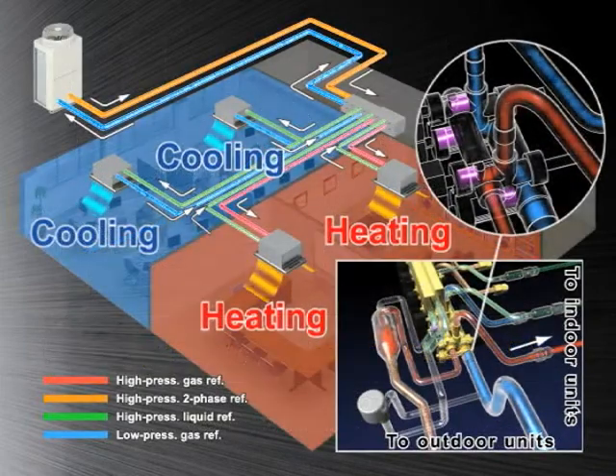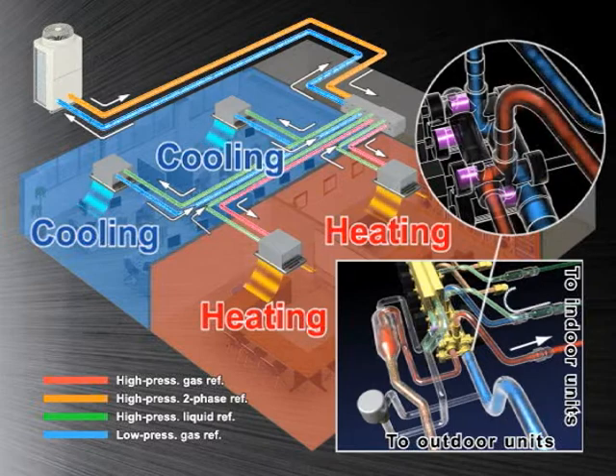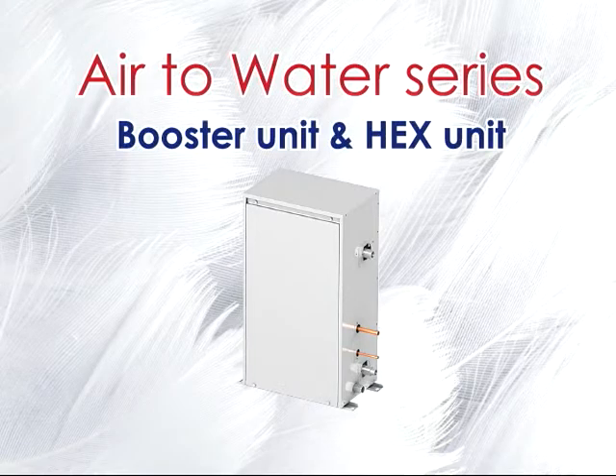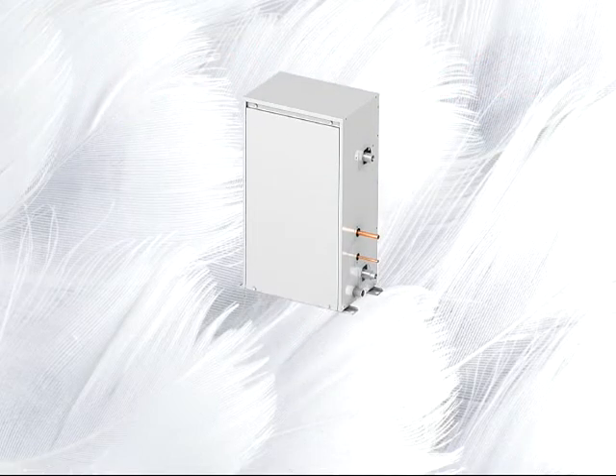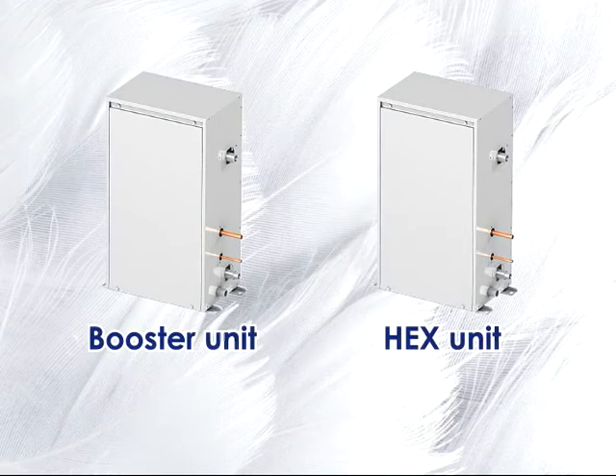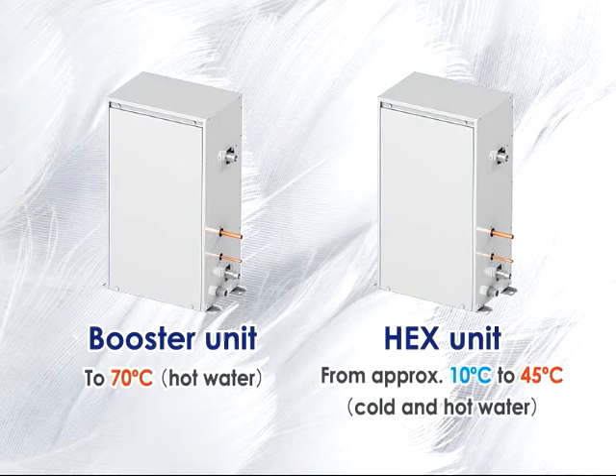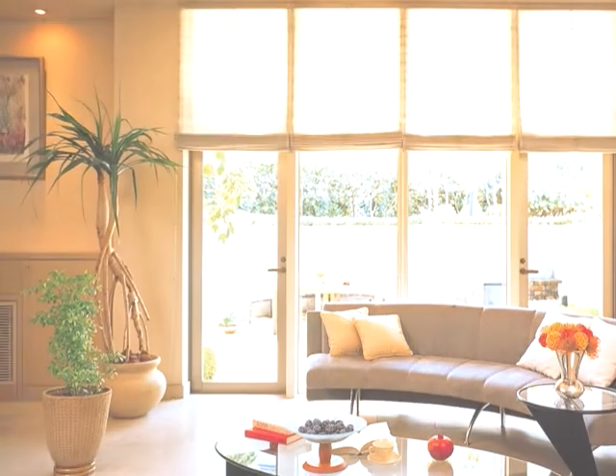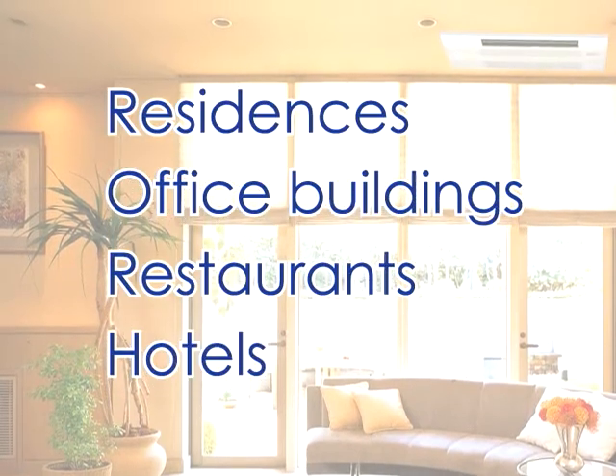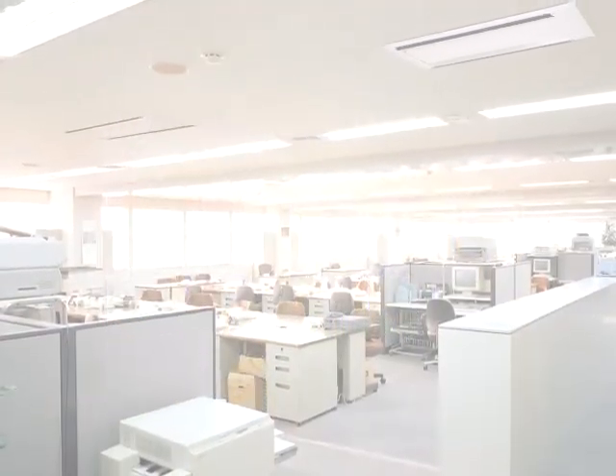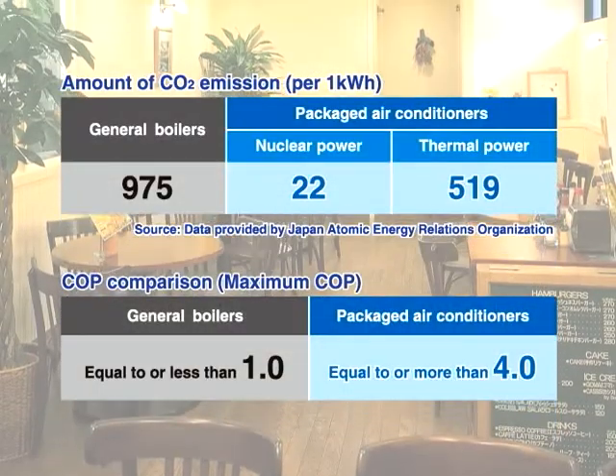This reuse of waste heat also applies to the air-to-water system, which supplies hot water with its heating cycle and utilizes the waste energy for cooling. The air-to-water series consists of 2 types: a booster unit and a heat exchanger unit. The booster unit offers hot water to a maximum of 70 degrees Celsius. The heat exchanger unit offers up to 45 degrees Celsius in heating mode and down to 10 degrees Celsius in cooling mode. Both units are suitable for residences, office buildings, restaurants, or hotels, providing an optimal indoor environment while reducing running costs and environmental impact.